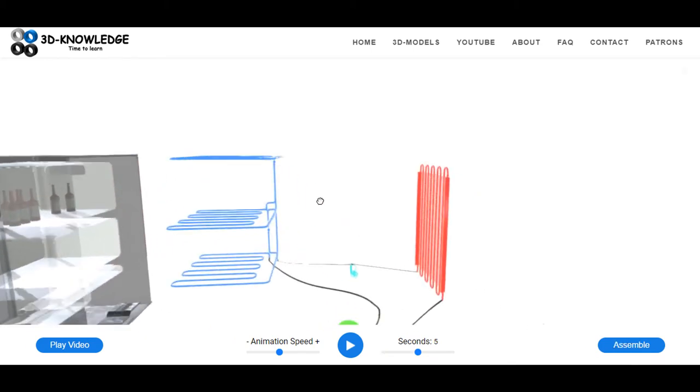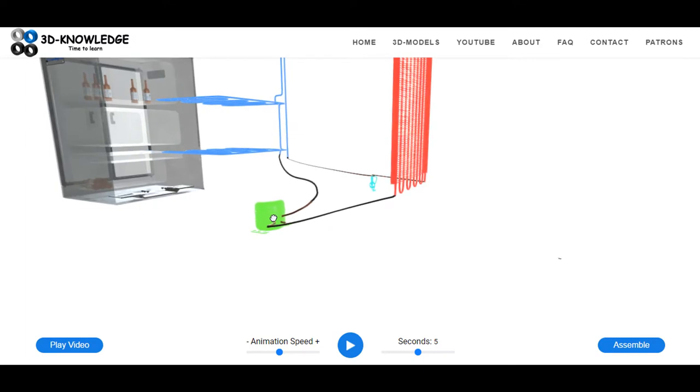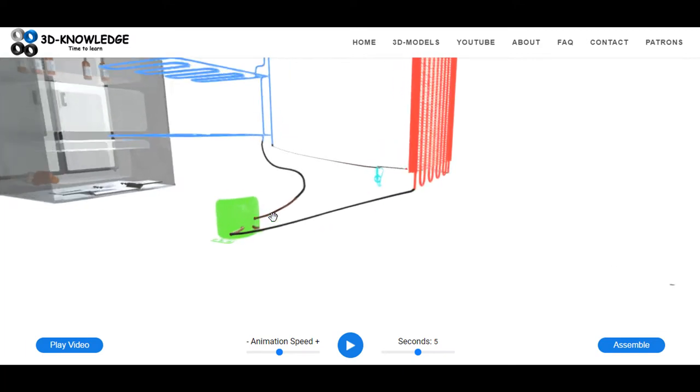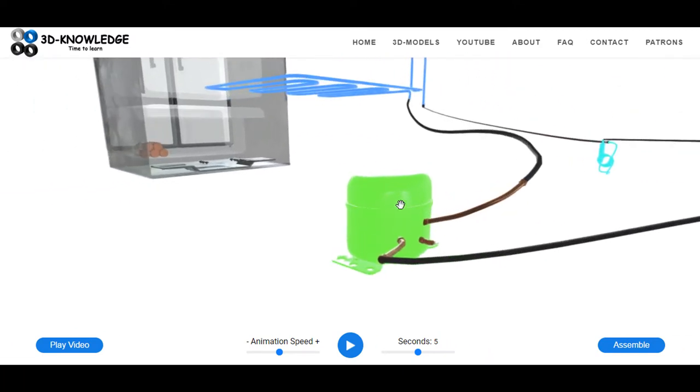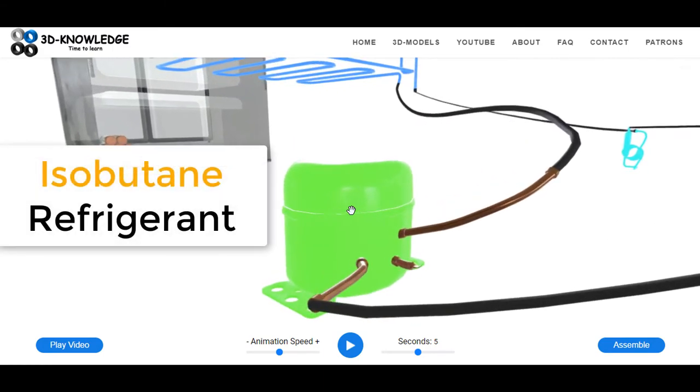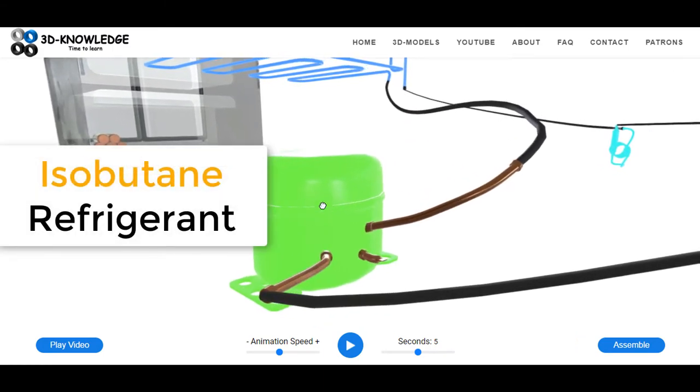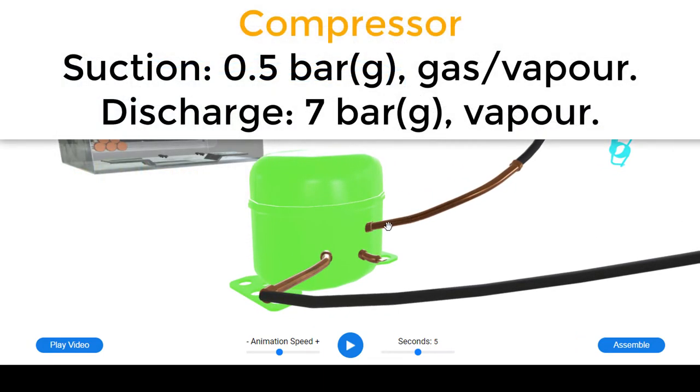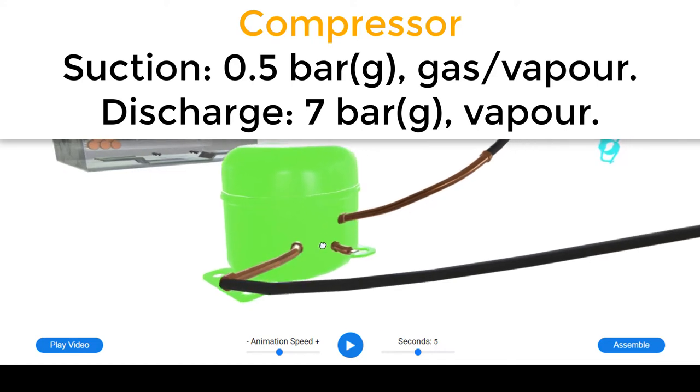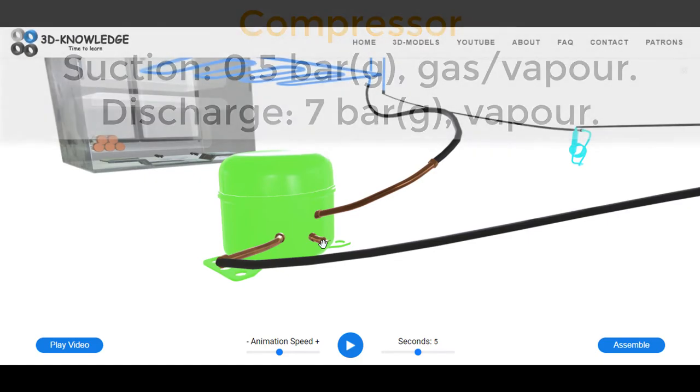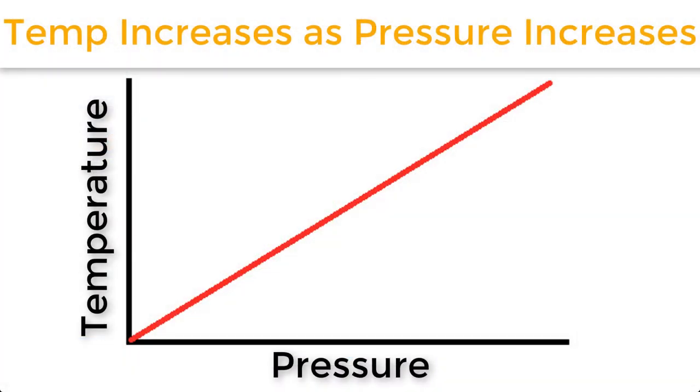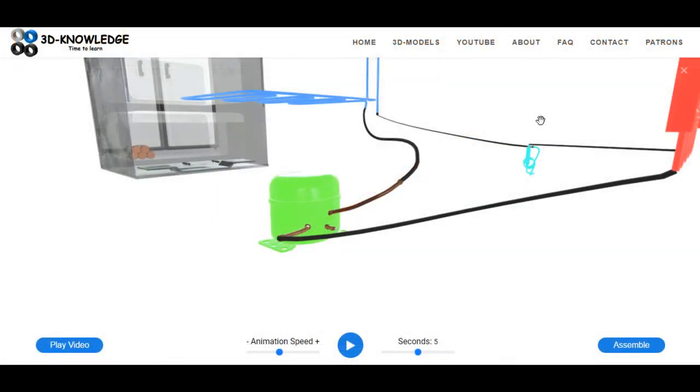So let's go to the compressor first. I think that's the most logical place to start. The compressor is drawing in a gas called isobutane. This is a type of refrigerant. It's going to draw that in on the low pressure side, so it's a low pressure, low temperature. It draws that gas in, it compresses it into a hot vapor. Whenever you compress a gas, the temperature will increase. This is one of the gas laws. So whenever you compress a gas, the temperature increases. So what we've done is just compress the gas. We've got a hot vapor out, and that's the exact opposite of what we wanted to achieve. Remember we're actually trying to cool something down here. That's what refrigeration is all about.